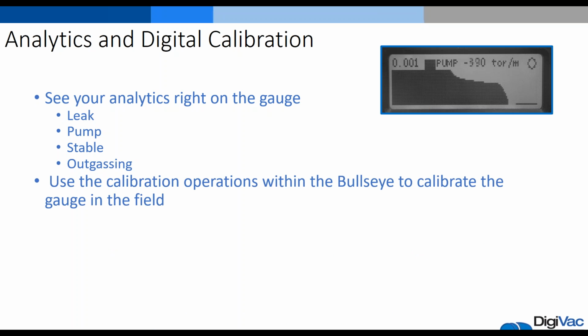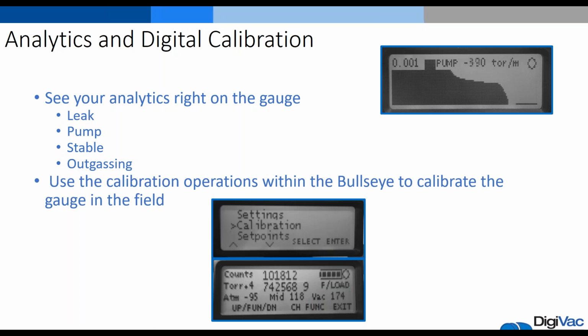You can also use the calibration operations within the Bullseye to calibrate the gauge in the field. And to do that, as I said before, you would go into your settings, switch down to calibration, and then on that screen you can set the different units for what's needed to work within your vacuum process.